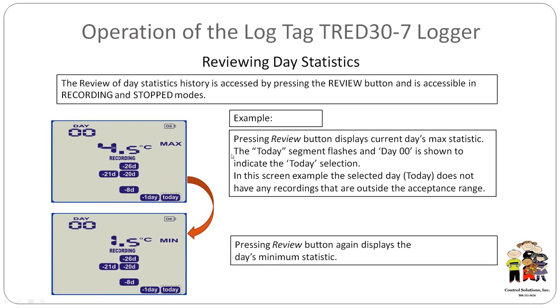So at midnight, I pushed the top button once, it's today, and it's going to say that I had a high temperature of 4.5 Celsius. By pushing the button the second time, it's going to scroll back in history another half a day, and it's going to say today, and this was the minimum. So these two values should be pretty much close to the same every day, unless you've changed your inventory volume. So if I came in Tuesday and I saw this, and I came in Wednesday, but let's say that the maximum temperature went up from 4.5 to maybe 7, it's an indication that we might want to do some investigation before we actually have an alarm condition.